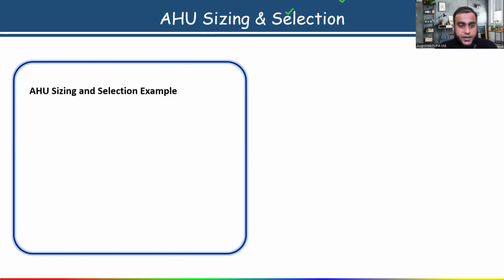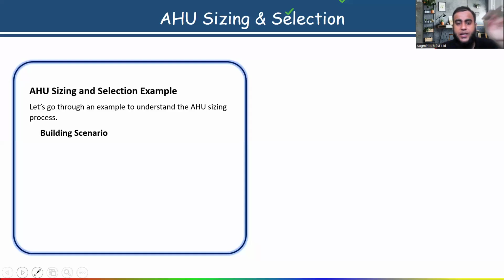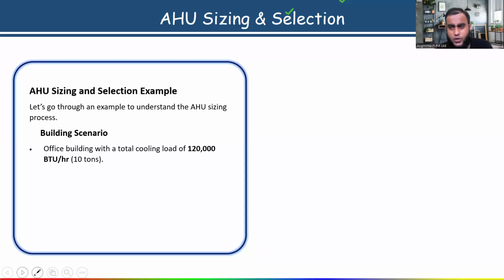So in this example, let us go through an example to understand the AHU sizing process. Suppose the building scenario, we are designing for an office building, with a total, suppose we have done the cooling load calculation with the help of software, suppose HAP software, Trace 700, or manual heat load calculation by E20 method, or general methods are also there. So here the building scenario is given, office building with a total cooling load. Total cooling load means they have given the sensible. Here I am just showing you the sensible load, okay? Because to calculate the airflow, we only need the sensible load, na? So the total cooling load or sensible load value is given here, 1,20,000 BTU per hour, okay? 10 ton. Is it clear?